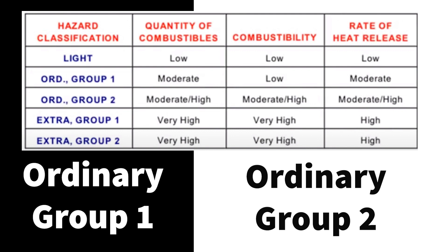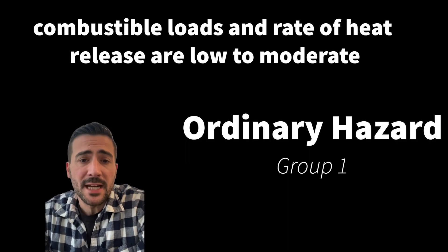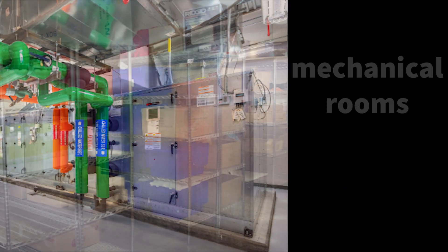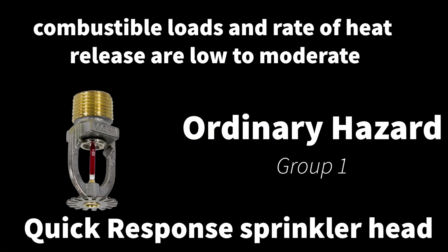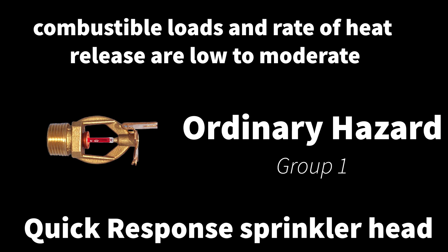Starting with ordinary Group 1: combustible loads and rate of heat release are low to moderate. Some examples are parking garages, kitchens, mechanical rooms, and storage rooms where stockpiles of combustibles do not exceed eight feet. With combustible loads and rate of heat release low to moderate, that gives us the ability to use the quick response fire sprinkler head in ordinary hazard Group 1. This head is going to keep temperatures lower, increasing the chance of survivability and escape, just like we would use it in light hazard occupancy.